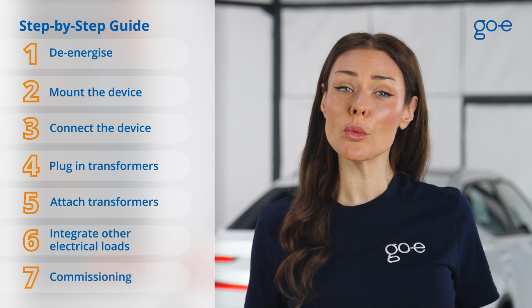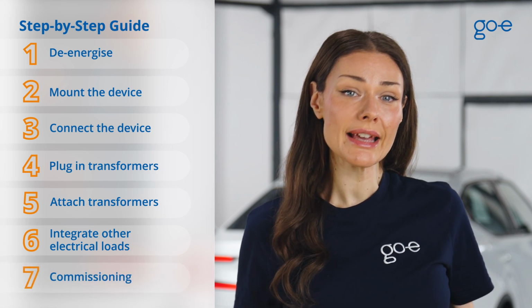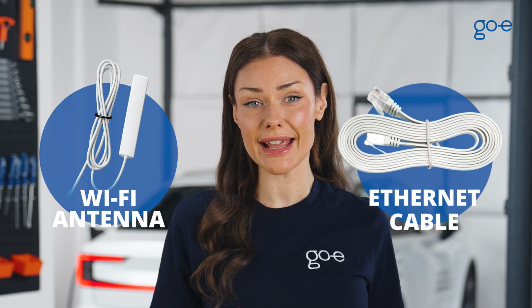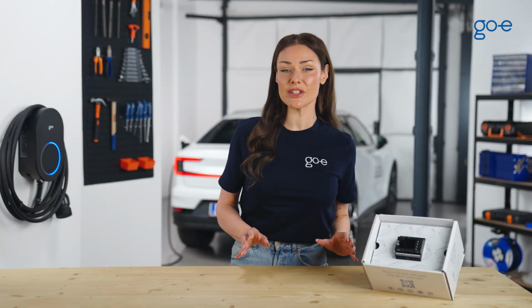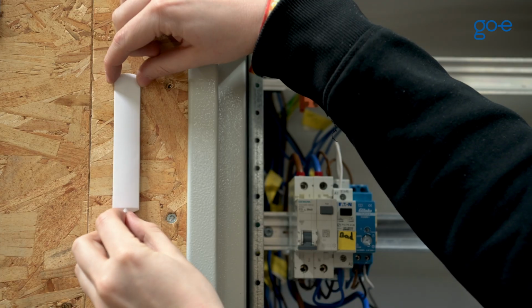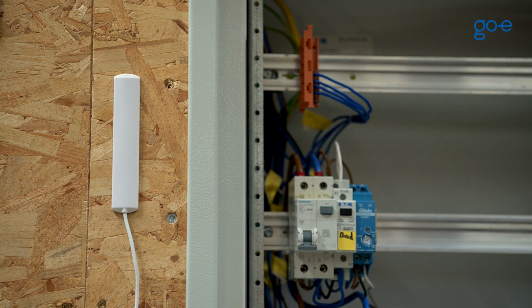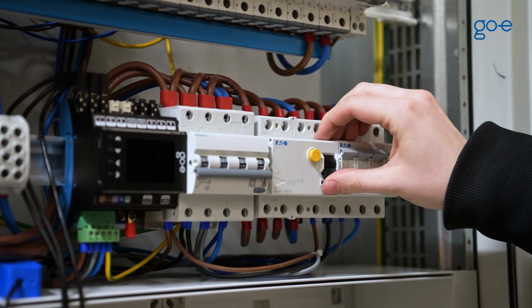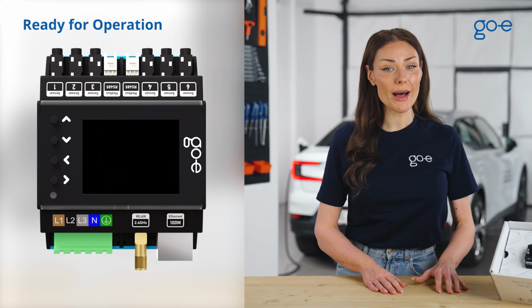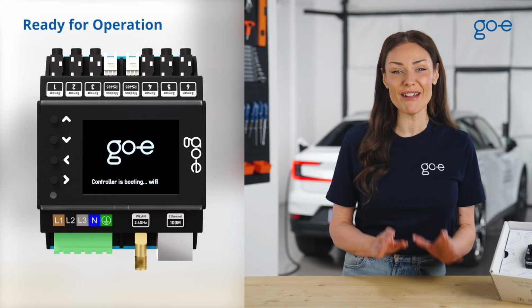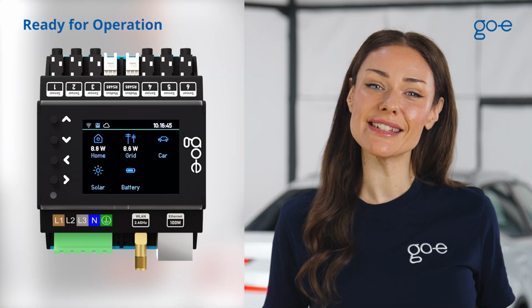Step 7, depending on which connection options you have available to you, connect the Wi-Fi antenna, LAN, or Ethernet cable to the GoE controller. For the best reception, route the flat Wi-Fi antenna cable outside the distribution board and attach the antenna head there. Once you've installed all the current transformers you need, you can restore the power supply. The GoE controller will now power up, and once the system has booted, it's ready for operation. At this stage, you'll probably see incorrect measurement values on the display. That's because we still need to assign the correct phase and category to each sensor. All right, let's move on to the initial configuration of the GoE controller.